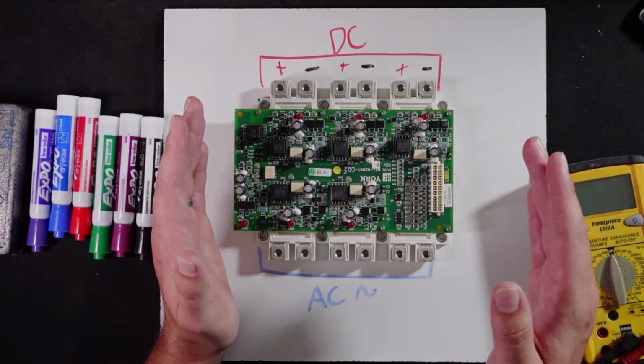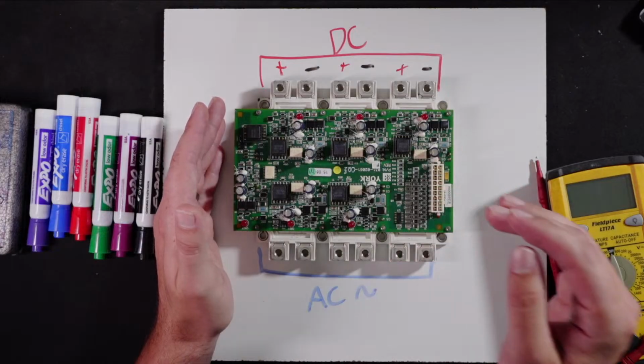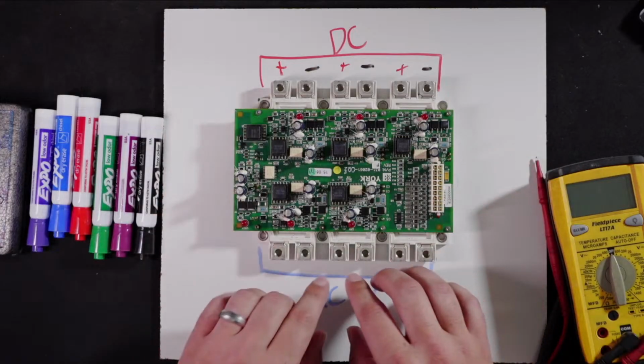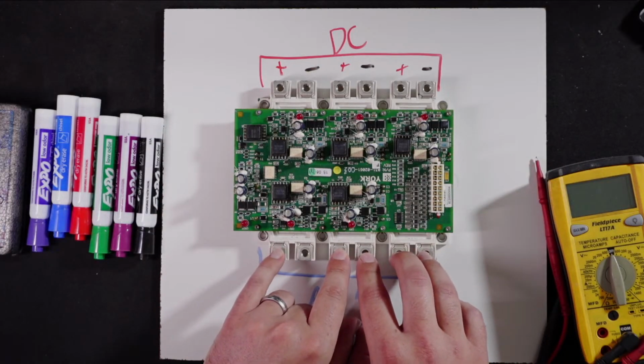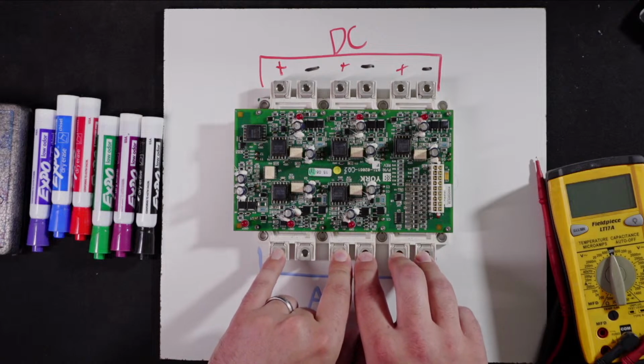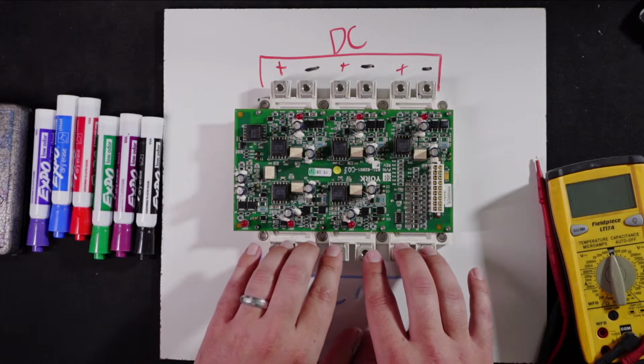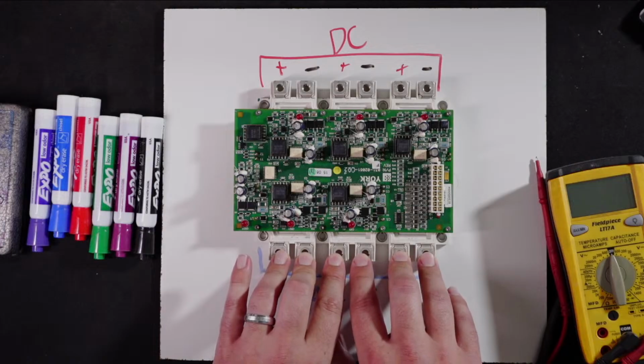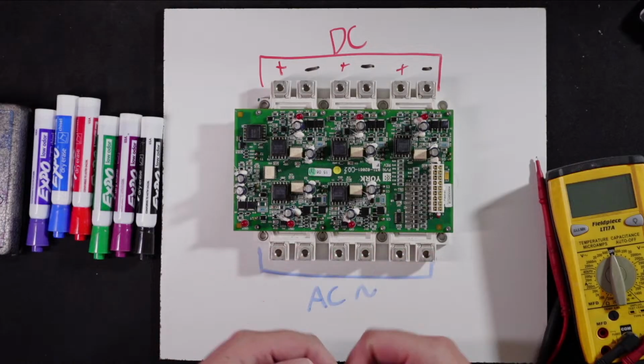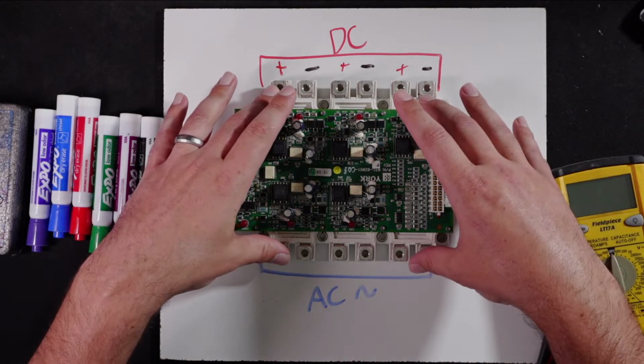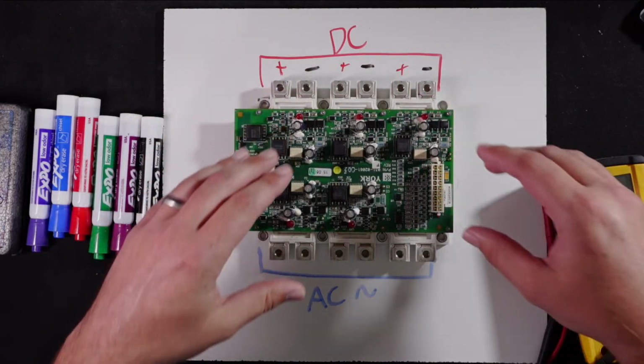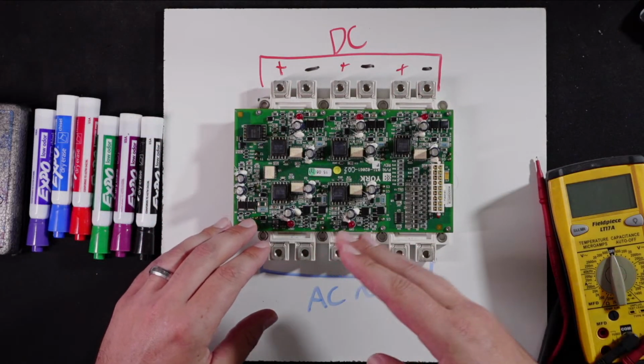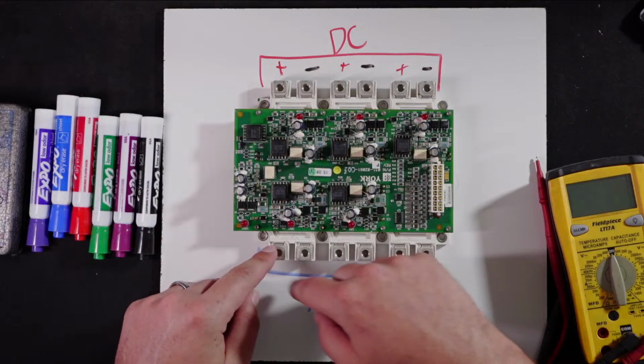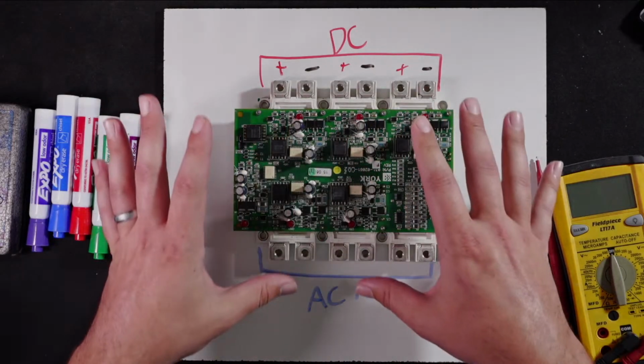So these fail for a couple of reasons. One, and this one's less likely, the motor side, which is over here, the motor side could be what failed. The motor failing, causing an overcurrent condition or something here in the bus, or maybe it caused a backfeed where one gate fed into the other gate and it caused an internal failure.